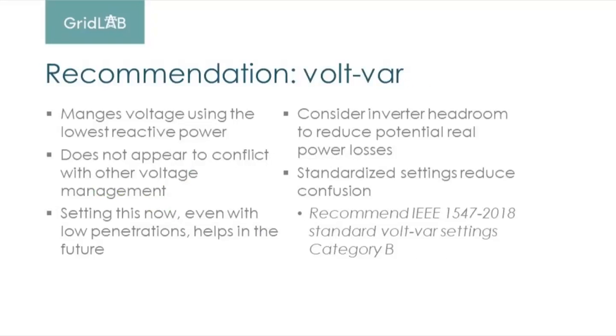And then something else that's important: we've heard some utilities saying, we don't want to implement that now. We don't really know what we want now. So we're going to deploy smart inverters at unity, running at fixed power factor. And when we figure it out later, we'll come back and make them install communications, and then we'll set it to something else. We really believe that these settings are a way to future-proof. You don't want to have to go back later and fix legacy smart inverters because you're not ready with exactly the perfect setting. And we think the default curve, we're recommending the default Category B volt-VAR curve from the 1547 standard, reduces confusion and works for most systems most of the time.